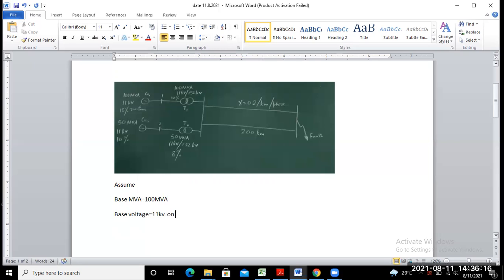Okay. So on the transformer low voltage side, just here mention transformer LV side, up to LV side. Okay. If you find any per unit reactance value after the transformer high voltage side, then you choose 132 kilovolt as the base voltage. Okay, because if you find the per unit reactance value of this transmission line, here you need to use 132 kilovolt as the base on the transformer HV side.